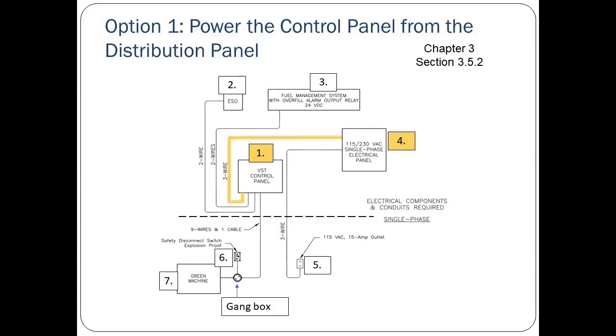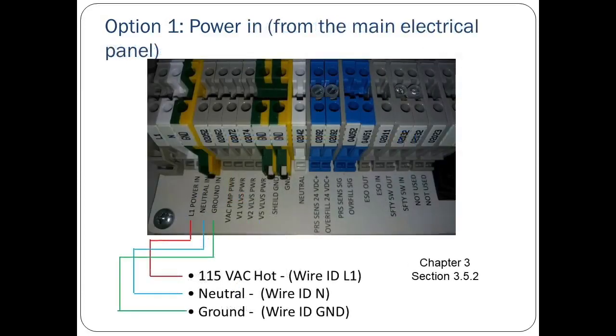Let's talk about Option 1, specifically about the wiring between the electrical panel and the VST control panel. The size breaker required for this connection is 20 amps. The power wires must be terminated at these locations inside the VST control panel. Label the breaker on which the VST control panel is connected with the name Green Machine in all caps so that a service tech can quickly figure out which breaker it is.